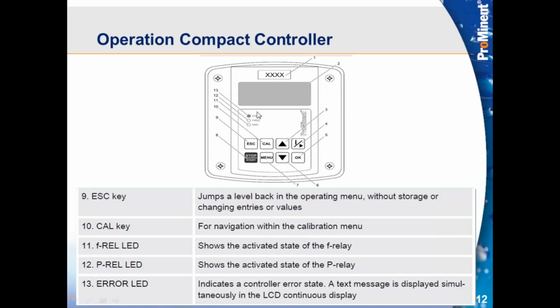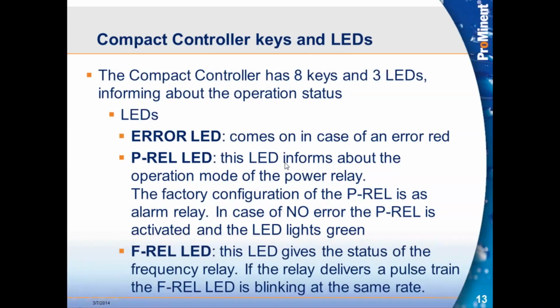We have some LEDs. We'll talk about the LEDs here, but they're just below the digital display. We have an error LED. It comes on red if the unit is in error for any reason. Whenever units go into error, they stop the control outputs, or they set the control outputs to stop the device that we're controlling. So if we're in the 4 to 20 milliamp range, that control output would go to 4 milliamps. We have a pacing relay, or the frequency relay actually, at the bottom. That will flash at the same rate as that pacing relay is closing. So we can see that flash each time it goes out.